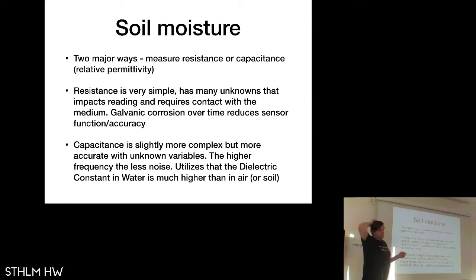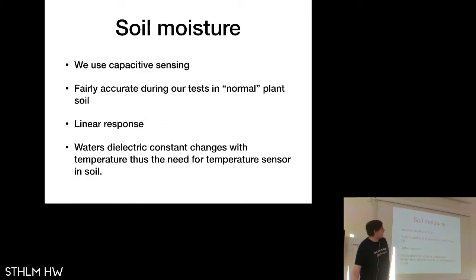It utilizes the fact that water has a much bigger dielectric constant than air or soil. I think air is around 1, vacuum is 1, water at 20 degrees is 80, and soil is about 4. So you can use that fact to calculate the soil moisture more accurately. I can't tell you how accurate it is, because we haven't really measured that, but it is fairly accurate during our tests. I would say somewhere in the region of plus or minus 5% or better. It happens that the response from the sensor is extremely linear, which is very nice. So you don't have to do any complex mathematics to convert it to a percentage.